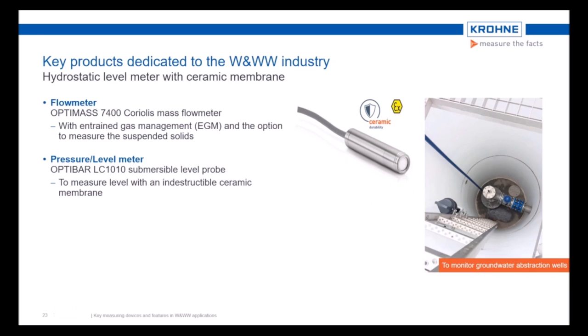Actually, the next key device is a pressure device, but we are measuring the level with it. So indeed, we are talking about a hydrostatic submersible level probe, which is often used in abstraction deep water wells to measure the groundwater level. The great advantage of this device is the material of the membrane. Very often metallic membranes are used, which are very sensitive against mechanical impacts or strokes or any other bumping influence, even dirt from the process. Therefore, operators are making use of the indestructible ceramic membrane, which the OptiBar LC1010 brings with its standard configuration.